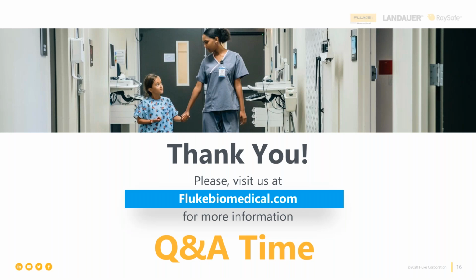Another question here is, what is metrology? I hope I pronounced that correctly. Metrology is the science of accuracy, determining accuracy. That's what metrology is. And when you make a measurement as part of testing a medical device, it is a form of calibration. You are making a metrologically important measurement that determines the safety and effectiveness of the medical device. Metrology is critical. If you've never heard that term before, you're hearing it now.